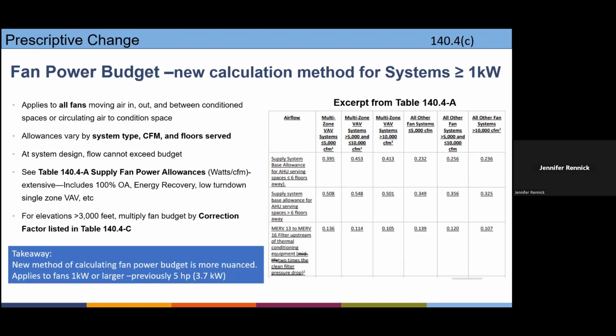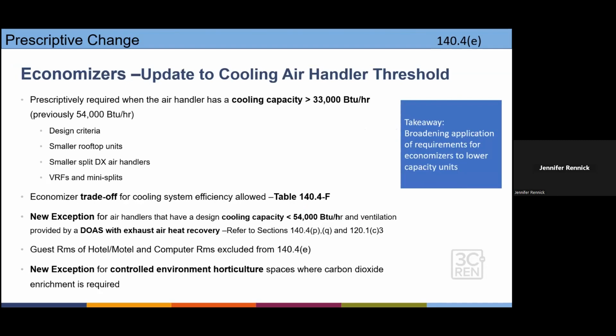So if you're a mechanical engineer on the call, you're definitely going to want to look through all the tables. You would enter the table based on whether it's a VAV system and how much CFM of air you are conditioning. Then on the left column, you look at whether, for example in the top one, it's serving space less than or equal to 6 floors away. That's where the size of the building comes in. It also kicks in whether or not you've got a MERV 13 filter or higher upstream of the thermal conditioning equipment, plus 2 times the clean filter pressure drop, et cetera. So it's nuanced, and you're going to want to take a look at that.